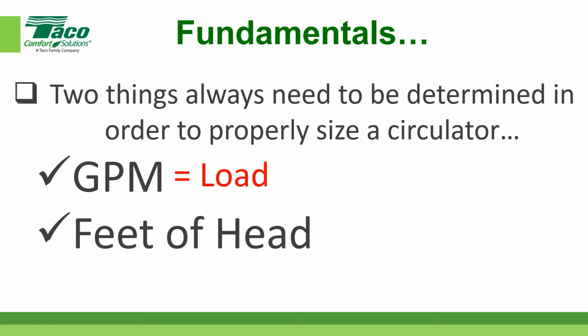So there's one example. But I also have to remind everybody, you can also change your layout pattern and still achieve roughly the same thing. If I went to either a serpentine counterflow or a spiral counterflow layout pattern, I could still achieve a fairly even floor surface temperature profile in lieu of doubling the GPM number. Because when we go from a 20 to a 10, we double the GPM requirement. So good question. I appreciate that.